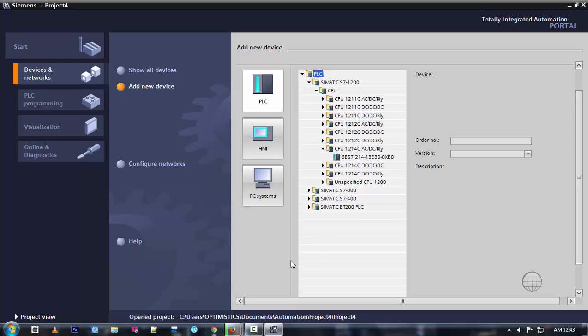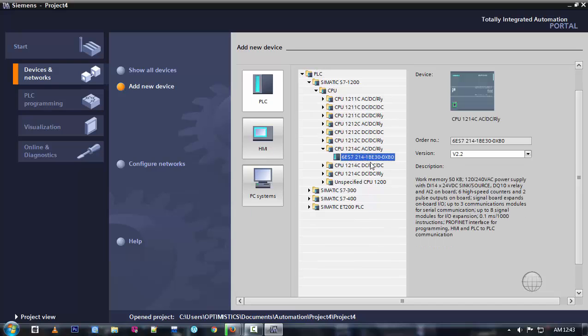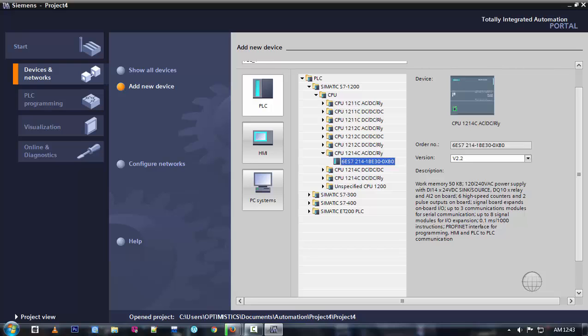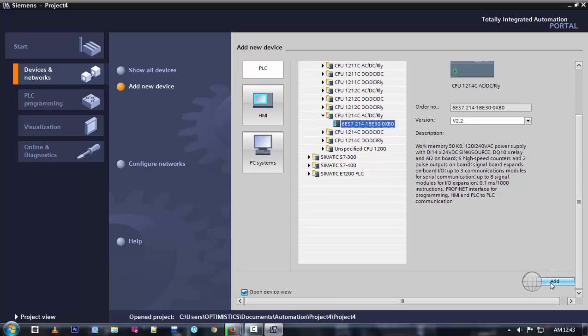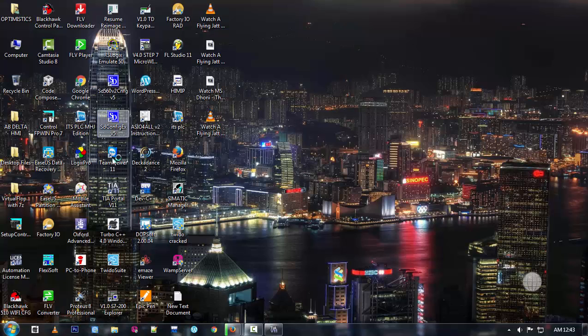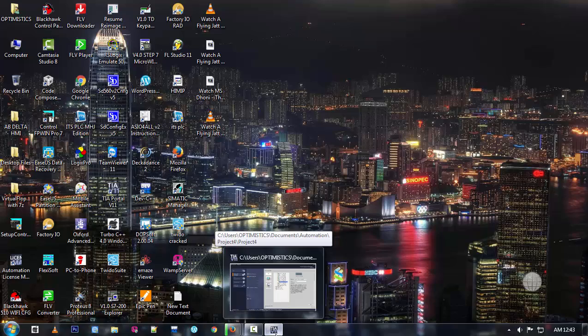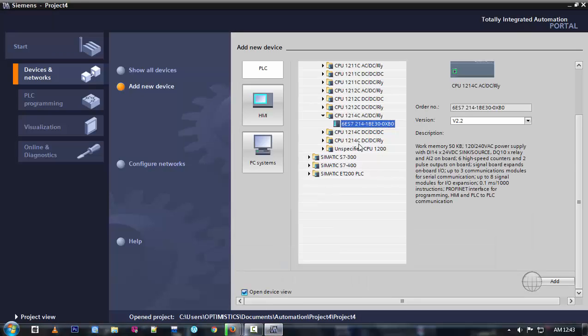When we try to add any device, it will not activate automatically — previously this Add button was not active. What I did is I have run this TIA Portal V11 software in administrative mode. You have to provide administrative privileges to this TIA Portal software; then only you will be able to add the device or configure devices. Okay friends, I'll show you now.